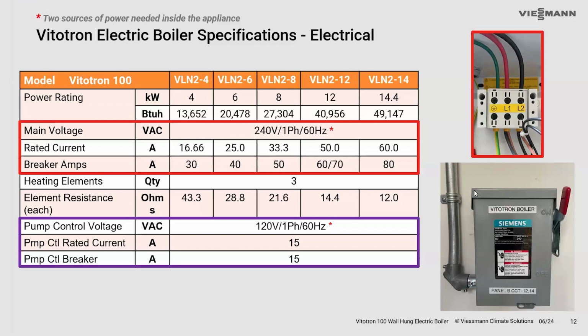But I just wanted to emphasize here, going back to one of the first slides that we looked at, on the top, the red, I believe that's a crimson red, if I'm not mistaken, is outlining the 240 volt single phase requirement up in the top right there of your incoming power. And this is the 240 volt that's going to essentially be used by the elements to actually provide the space heating. On the bottom, we have a purple, maybe a plum purple. That one there is a 120 volt connection, and that's separate.